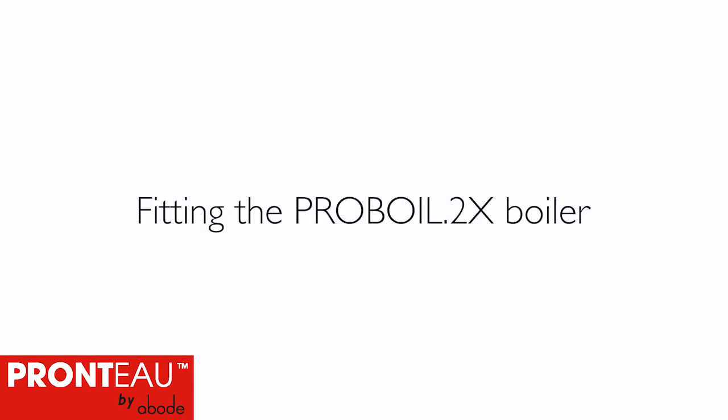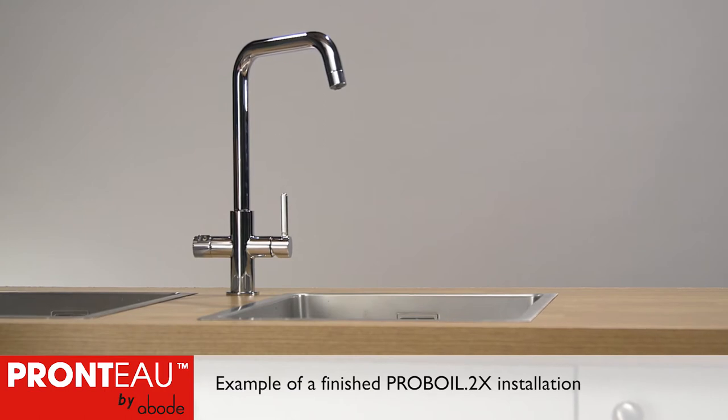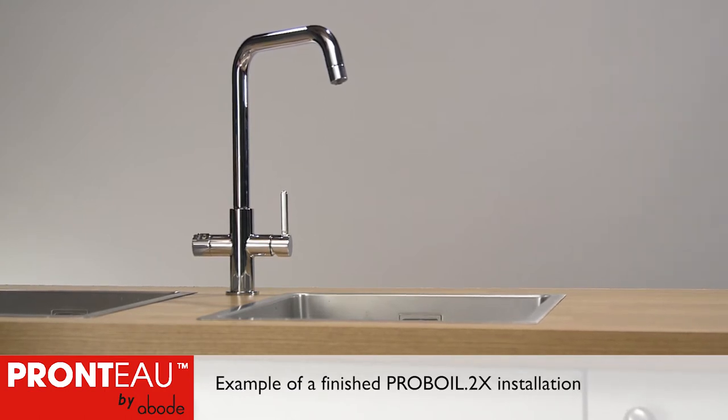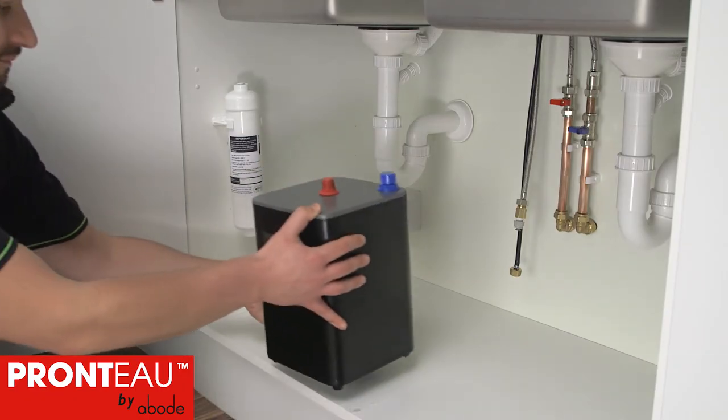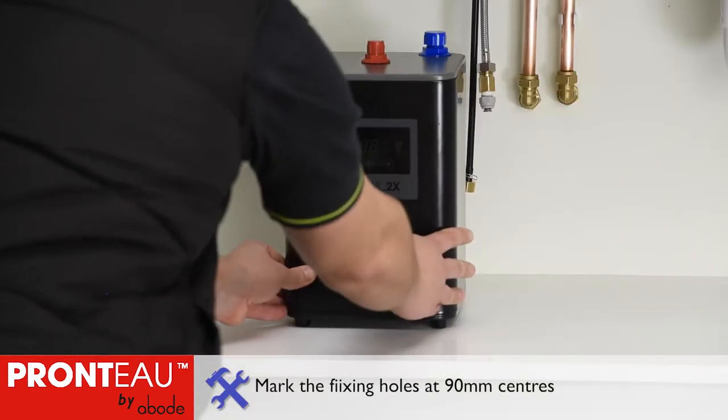You're now ready to install the boiler. Refer to the supplied installation guide and check the preparation steps before connecting the boiler. Before fitting the Proboil 2X boiler, an appropriate Pronteau 3-in-1 mixer tap should have already been fitted. All pipework should be flushed and a 13 amp power supply should be within 1.4 metres of the boiler.